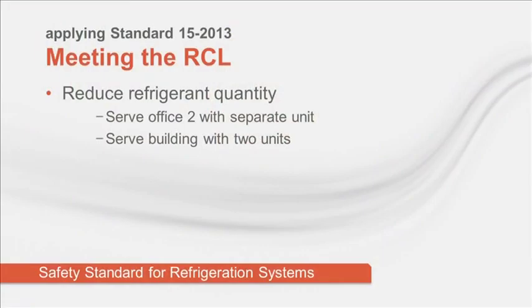But that doesn't mean VRF can't be used on this building. One solution is to serve Office 2 with a small, separate unit. A direct unit serving a single space will likely have a small enough charge to meet the RCL requirement. A second choice is to replace the single VRF system with 2 smaller systems. Either solution is acceptable as long as the RCL requirement is met for all rooms. So far, the solutions have focused on reducing refrigerant charge. But what about increasing dilution volume?